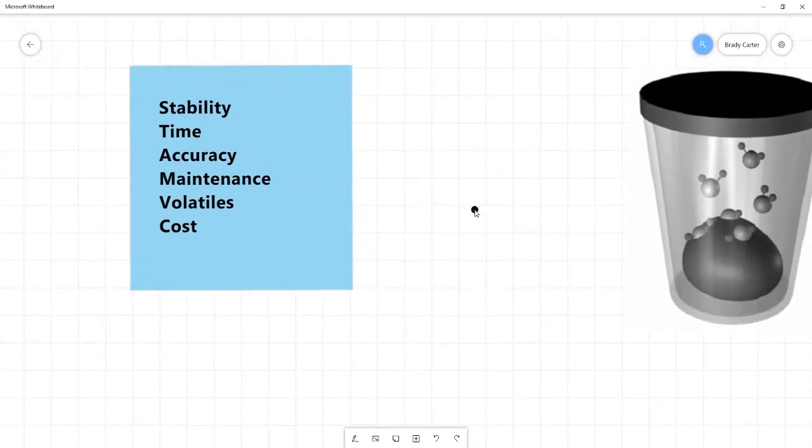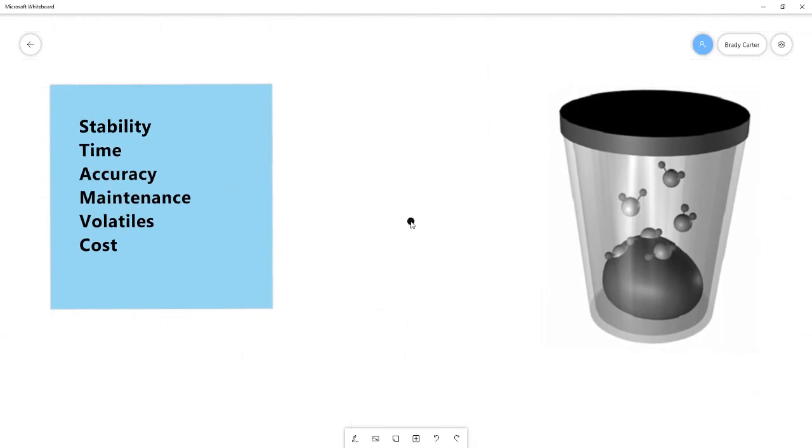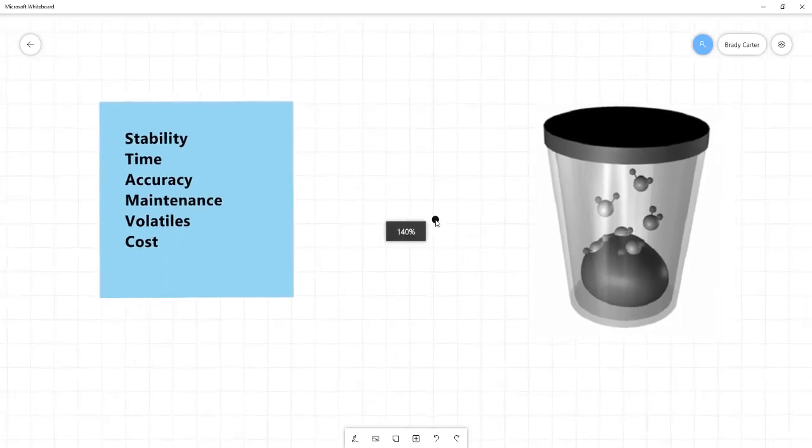And first, before we start our discussion, we need to highlight what a water activity measurement consists of. The thing that's common among all water activity measurement methods is that a sample is placed inside of a sealed chamber, and then water escapes out of that sample. And over time, the headspace will come to equilibrium with the same water vapor pressure as in the sample, so that the relative humidity measured in this chamber, called the equilibrium relative humidity, will be the same as the water activity of the sample. And the methods differ on how they actually measure that vapor pressure or that relative humidity.